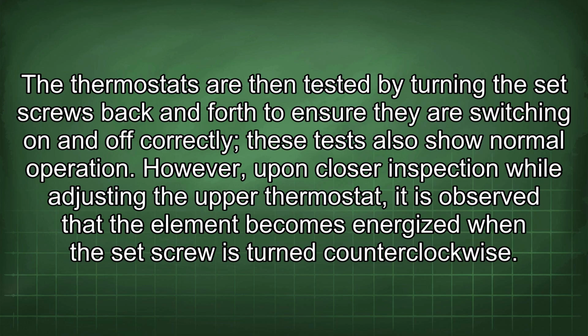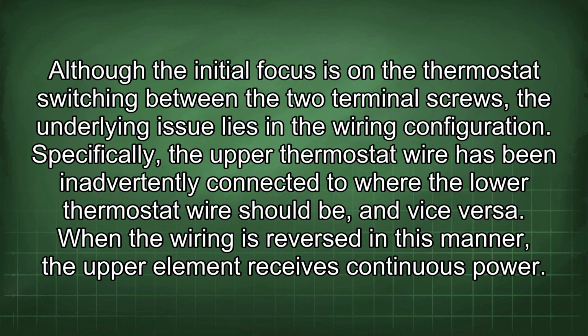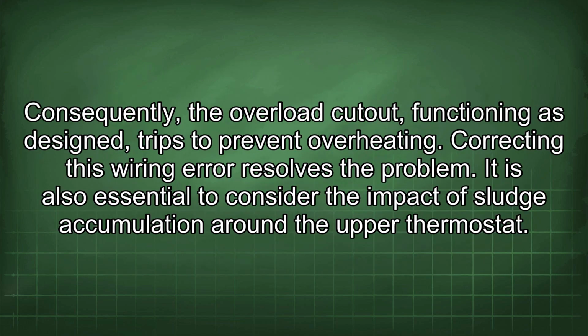However, upon closer inspection while adjusting the upper thermostat, it is observed that the element becomes energized when the set screw is turned counterclockwise. Although the initial focus is on the thermostat switching between the two terminal screws, the underlying issue lies in the wiring configuration. Specifically, the upper thermostat wire has been inadvertently connected to where the lower thermostat wire should be, and vice versa. When the wiring is reversed in this manner, the upper element receives continuous power. Consequently, the overload cutout, functioning as designed, trips to prevent overheating. Correcting this wiring error resolves the problem.